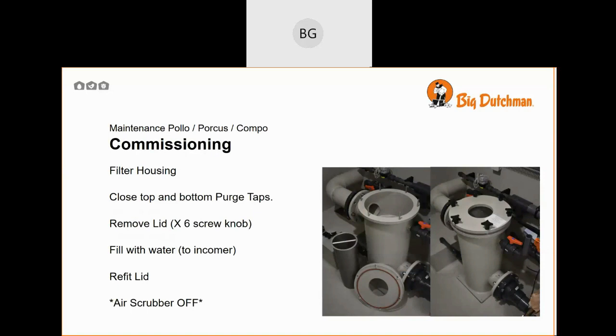For the filter housing, close the top and bottom purge taps, remove the lid, the 6 screw knobs, fill with water to the incoming pipe, and refit the lid. This must be done before starting the air scrubber. The filter will remain full when the pump is stopped. However, if the filter has been emptied, this can be unintentional, the filter must be refilled before restarting the pump.